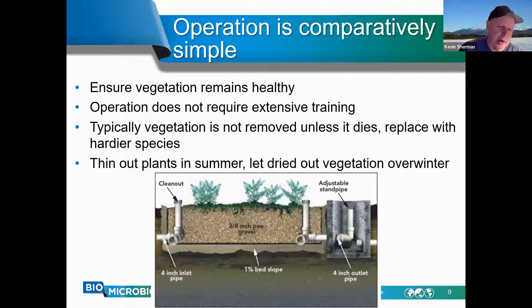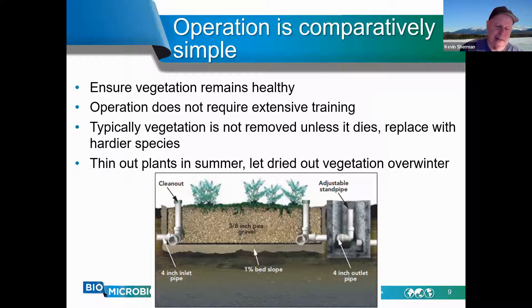You may learn of hardier species for your area over time. You can plant a trial plant in a constructed wetland to see how it does, and depending upon the location, they may need to be thinned out over the summer. This technology is capable of taking septic tank effluent — which is basically primary treatment, a BOD of about 140 and TSS of approximately 100 — and treating it down to secondary or better treatment levels, about 30/30 for BOD and TSS.